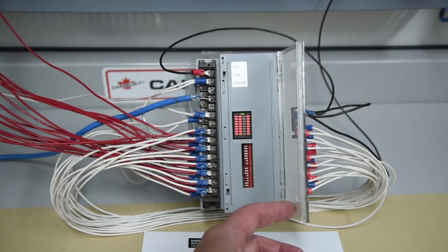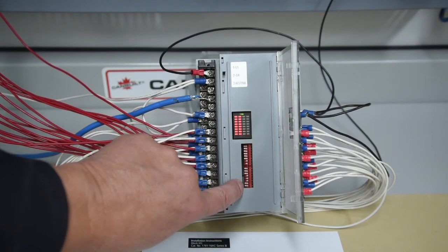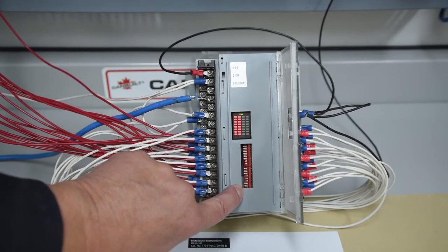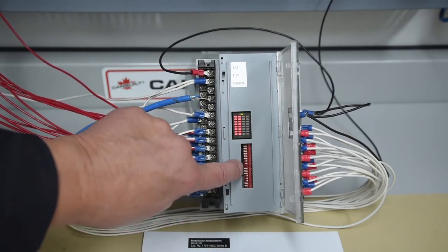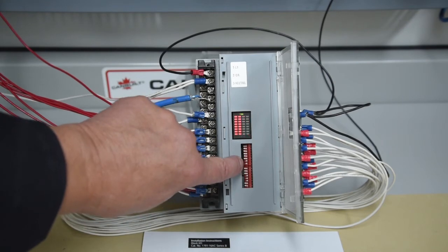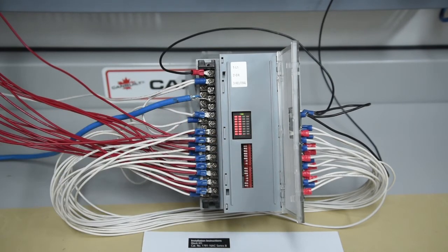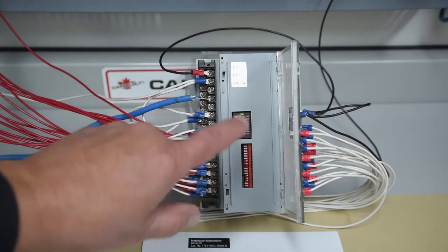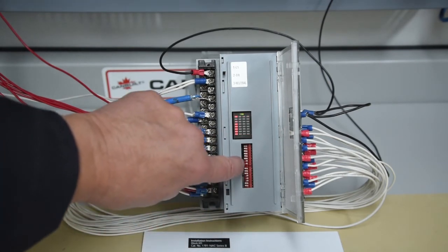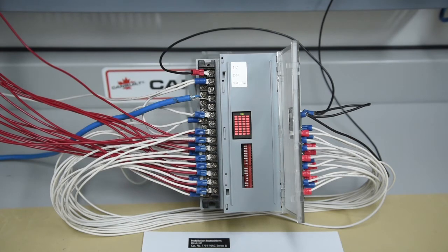So anyhow, to set things up, your bottom switches here are your starting quarter, your rack address unused, and then that's your speed there. And the rest of them basically for PLC5 are unused. Currently this is set for rack 7 and 230K. Now like I said, if you do a change to the switches, you have to power it down, power it up. It's just the way these old ones work.